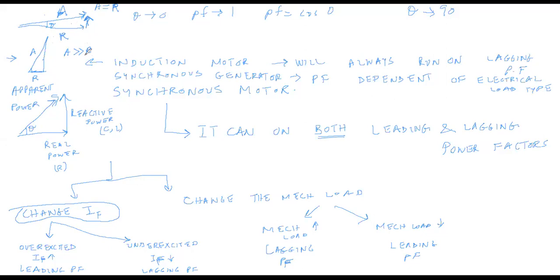So similarly, in order to have a power factor correction, you could make a synchronous motor run with a leading power factor, so that it can cancel out your lagging loads, and you make your power triangle look from this to this, where this side is more optimal for you, because in this way the real power consumed and the apparent power are almost equal, and K electric bills you for the apparent power.